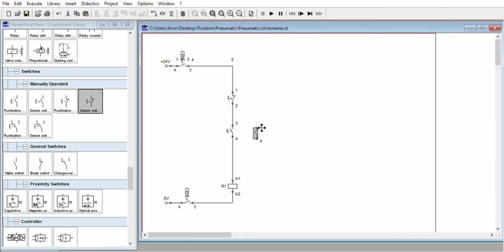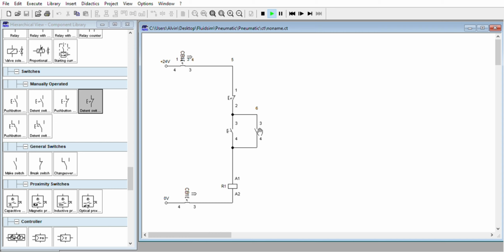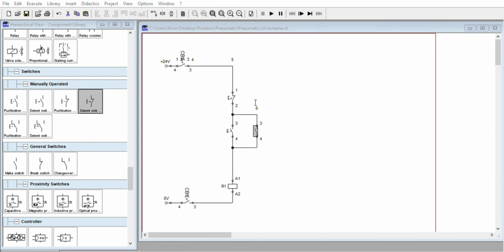Turn off. You cannot edit if you are not going to turn off. So parallel here, parallel here. Okay. Notice again here, see, why is this one not turning on? Because there is no label. So what should be the label here? If that is R1, we are going to label that one also as R1. Okay, right click. You can label this one, or double click, label R1. So in the laws of relay operation, magnetic switch, magnetic contactor, if this coil is labeled R1 and that auxiliary contact is labeled R1, that means this relay owns that one. So that magnetic contactor, magnetic switch, is the owner of this auxiliary contact.